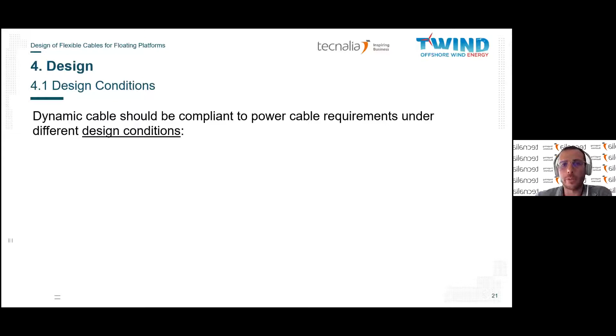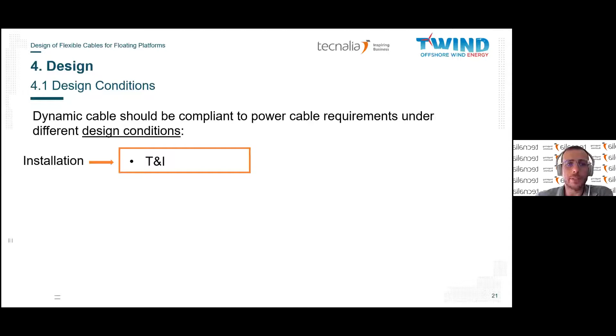Design methodology. In designing the dynamic cable, the designer shall take into account different design conditions in order to find a configuration that is compliant with the requirements of the power cable: design conditions during installation phases, transport, installation, and operation; and the different limit states: service, ultimate, fatigue, and accident. It's important to note that the cable manufacturer may provide different requirements, meaning different cable capacity curves for each stage of the design and life of the project.